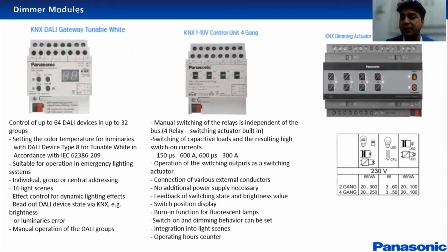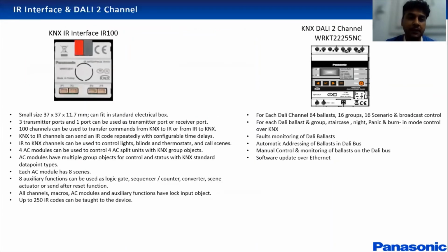Then we also have a universal dimmer in 2 different formats: 2-gang and 4-gang. For 2-gang, it is 300 watts per channel. For 4-gang, it is 250 watts per channel. We also have a KNX IR interface, using which you will be able to control and monitor your IR devices, like split ACs, TVs, or set-top boxes. This IR interface has a small footprint and 4 ports built into it. 3 ports can be used for transmitting and one port for receiving. You can configure this again on ETS. You can store up to 250 IR codes in the device. They can be taught and stored on the device.